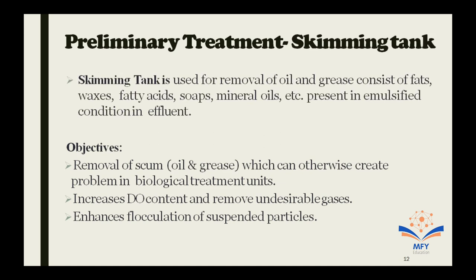Primary treatment: skimming tank. The skimming tank is used for removal of oil and grease, consisting of fats, waxes, fatty acids, soaps, mineral oils, etc., present in emulsified condition in effluent. These materials have low solubility in water, therefore are not readily available for biological treatment, and often accumulate on the surface in the form of scum, causing foul odor. The efficiency can be improved by aeration, chlorination or vacuum flotation.